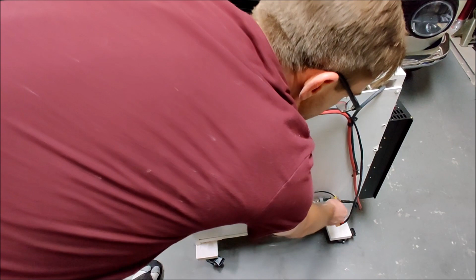The negative runs straight across and into the inverter. I tap a second negative off here that runs up to the bus bars to provide the negative for the bus bars. By tapping it off on the other side of the shunt, the power meter - which I forgot to wire - will be able to read how much energy runs through the bus bars and into, say, the 12-volt circuits.